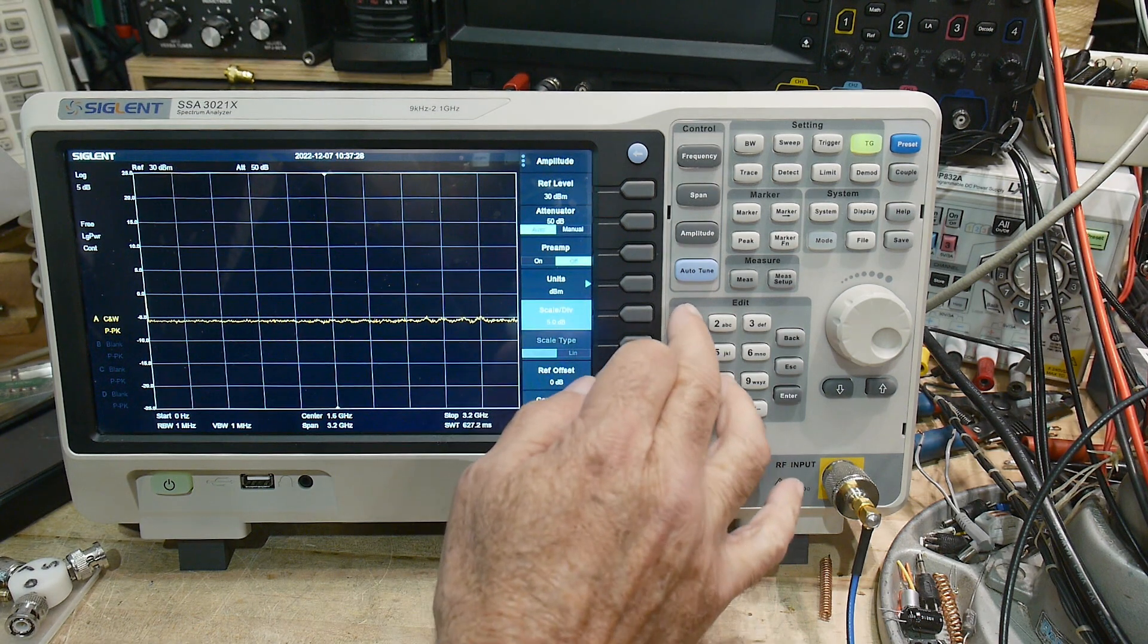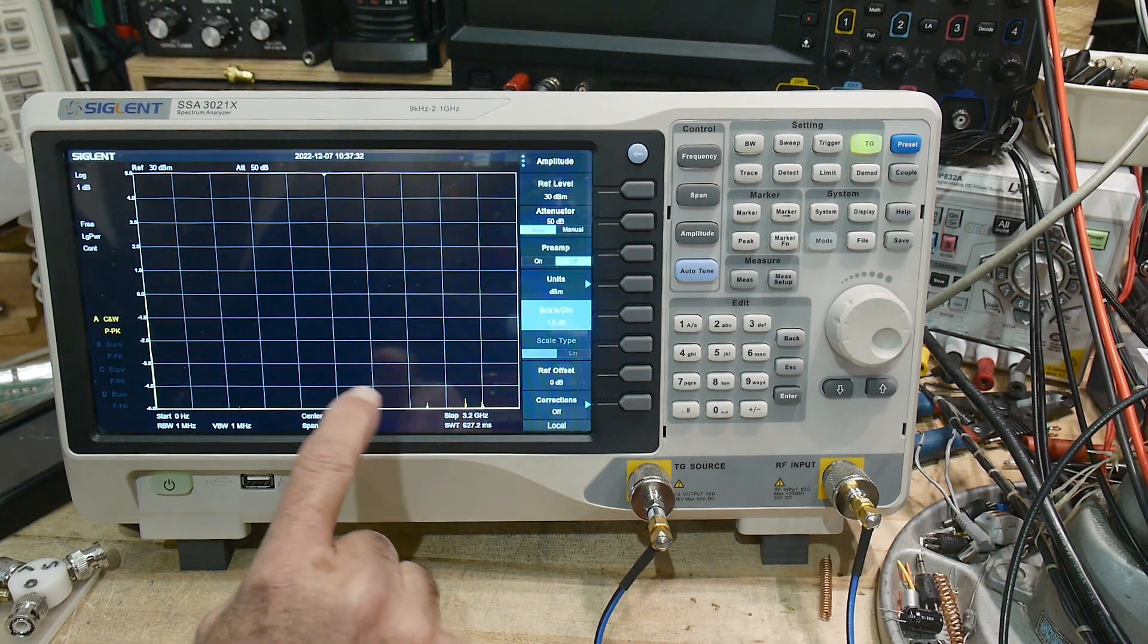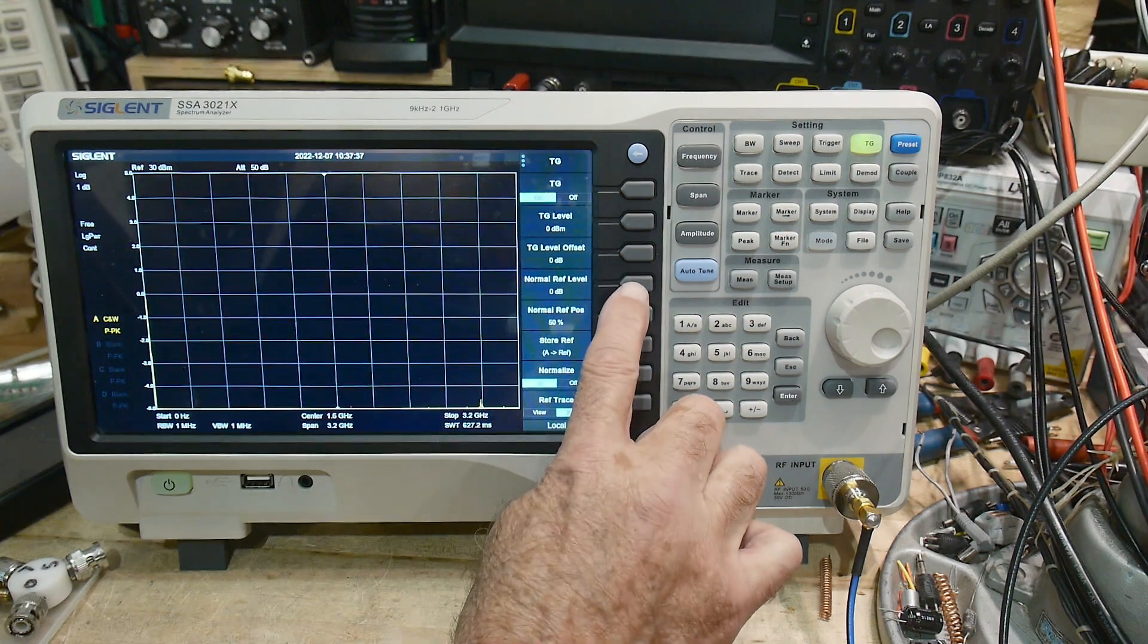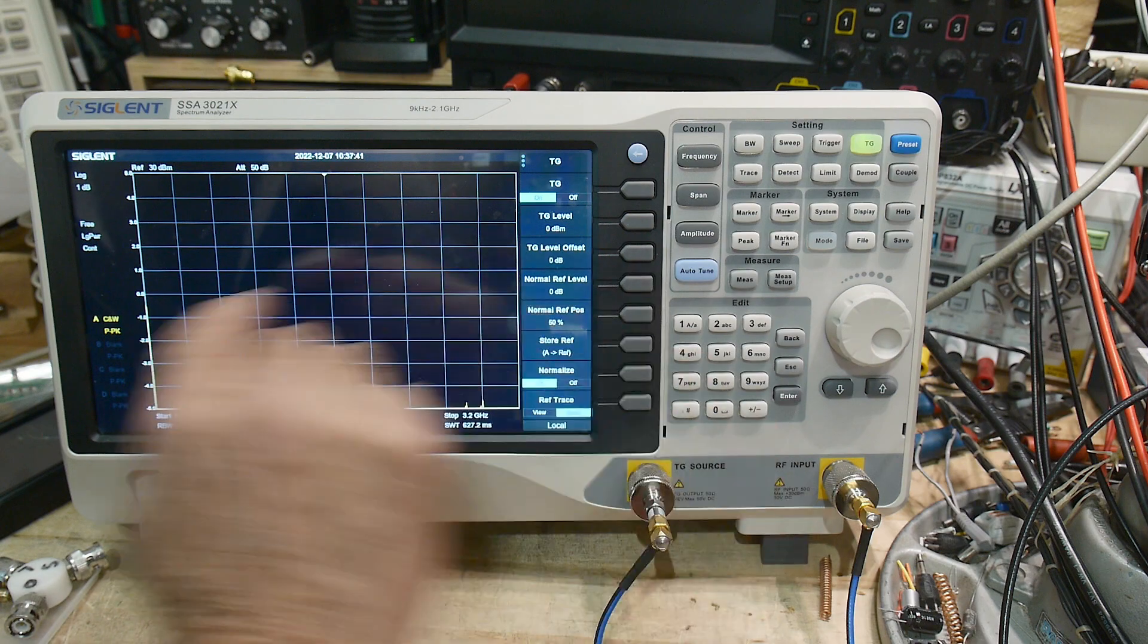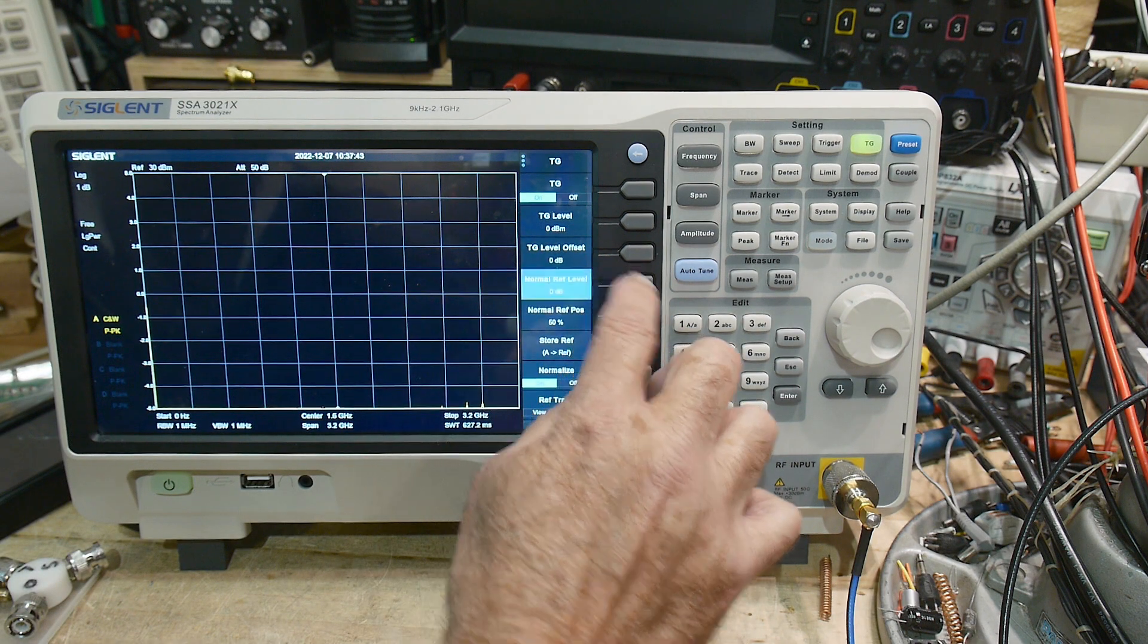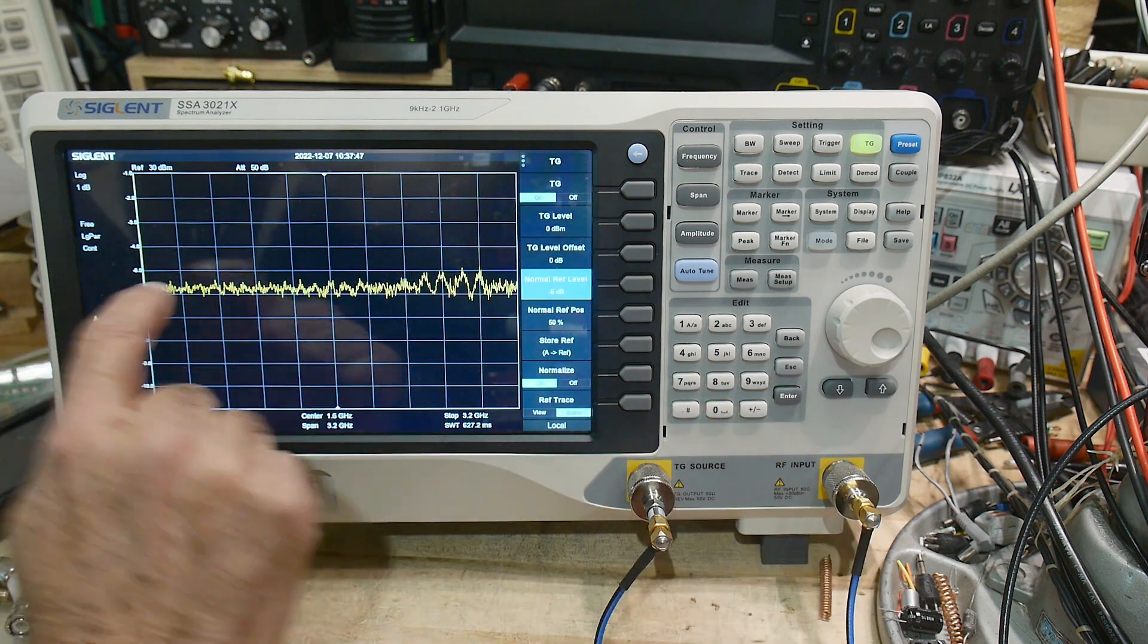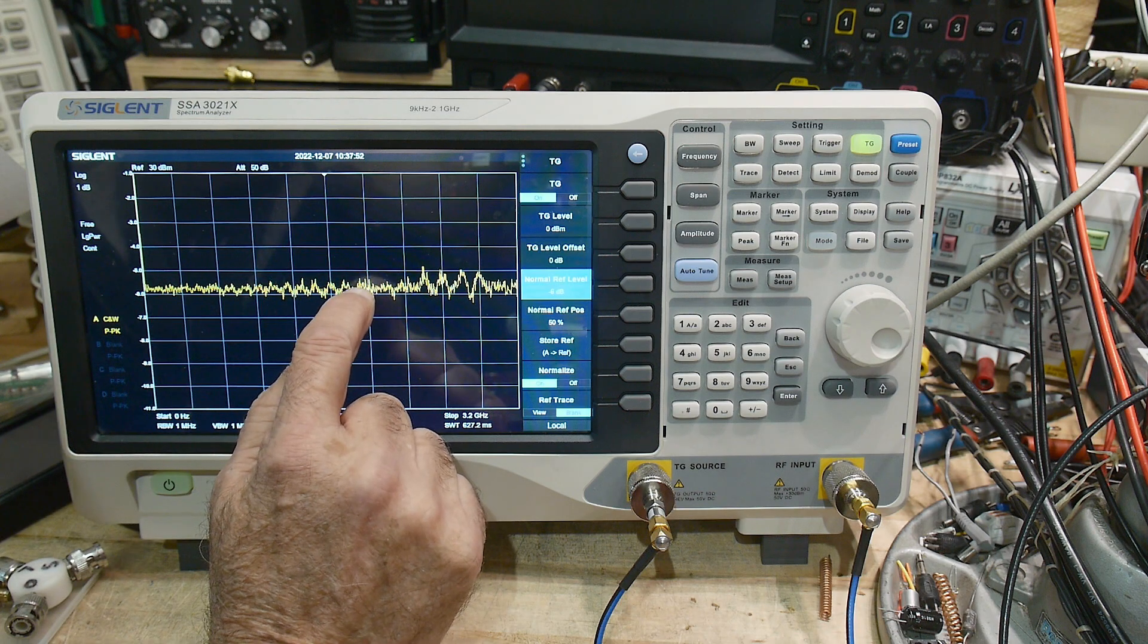Oops, it fell off the bottom. So how can we get it back up? Well, if we go back to that tracking generator, when we do this normalization, we can say we want to set the center point to minus 6. Now minus 6 will be right here at the 50% level, and that's what this is.